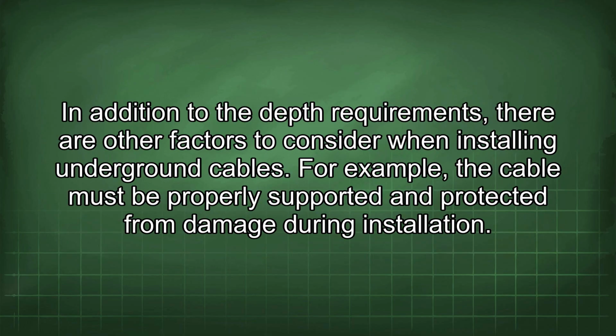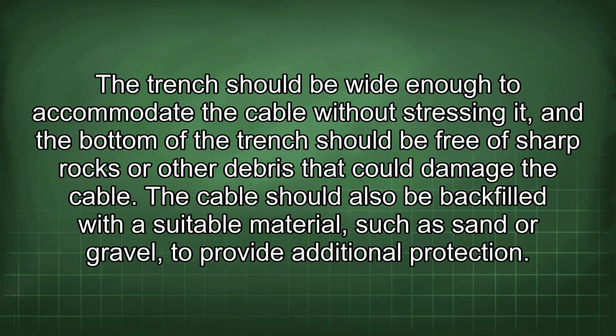In addition to the depth requirements, there are other factors to consider when installing underground cables. For example, the cable must be properly supported and protected from damage during installation. The trench should be wide enough to accommodate the cable without stressing it, and the bottom of the trench should be free of sharp rocks or other debris that could damage the cable. The cable should also be backfilled with a suitable material, such as sand or gravel, to provide additional protection.